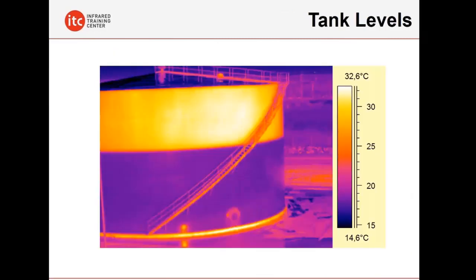Tanks. If you work for a large petrochemical facility, you've got tanks and a variety of different tanks. Perhaps the gauges aren't working properly for whatever reason, or you're trying to locate sludge that's perhaps built up in these tanks. Infrared used very successfully in the right conditions to locate tank levels, but also the presence of sludge in these vessels as well.